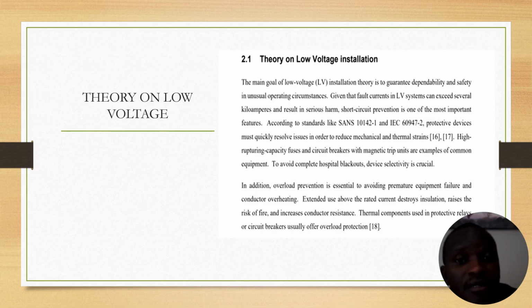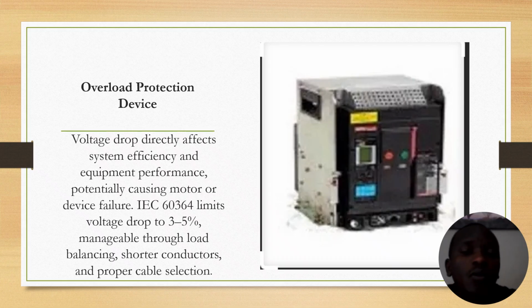According to standards like SANS 10142-1 and IEC 60947-2, protective devices must quickly resolve faults in order to reduce mechanical and thermal stresses. High rupturing capacity fuses and circuit breakers with magnetic trip units are examples of common equipment. To avoid complete hospital blackouts, device selectivity is crucial. This is the picture whereby you can see my protective device. This is the protective device, the overload protection device.